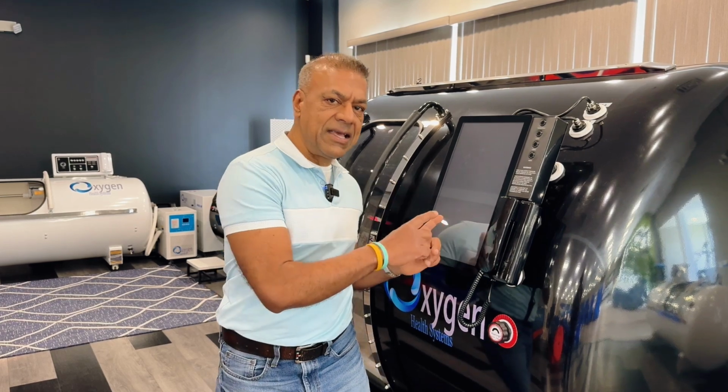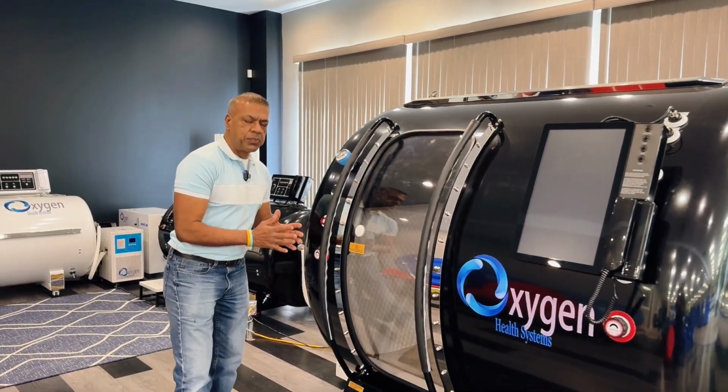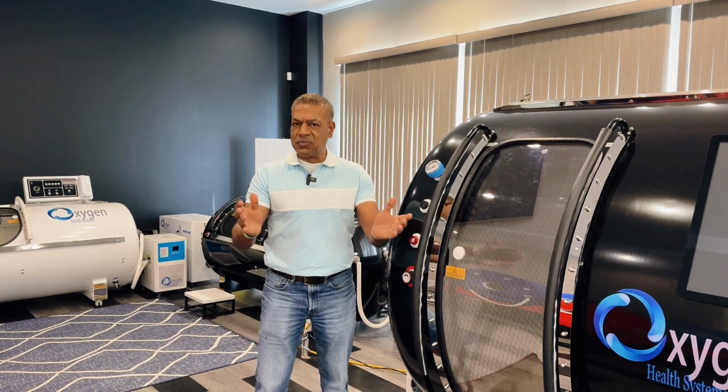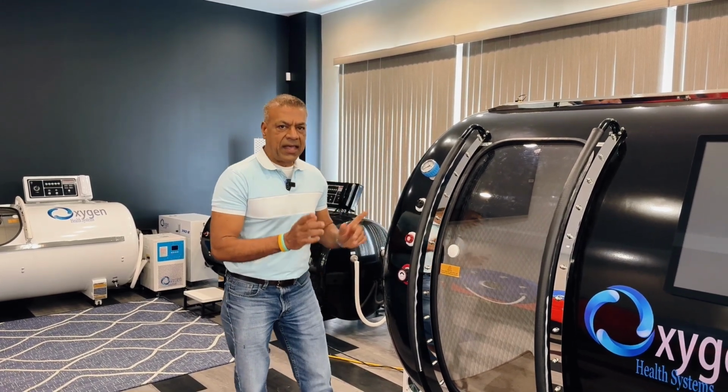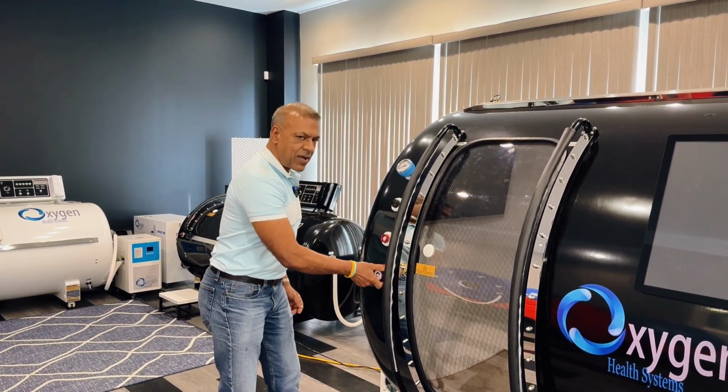The answer is no. The chamber itself is designed with an engineering concept in mind, which has been implemented here, that in the event of any power outage, there are enough safety features built into it, and you will not have to worry about depriving yourself of oxygen. Now, what I'll do, I will open them up all the way, because this is, let's say, an emergency situation, and then notice that the door would open. So here I go.